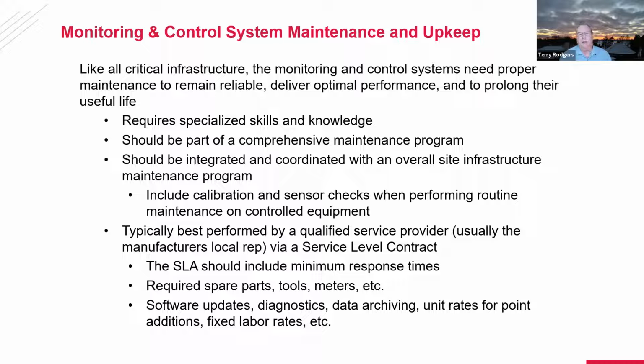I had an installation once and it was all commissioned, everything looked great. The system ran well, and then over time, it started to bog down. And I learned the difference between IP static and dynamic addresses, because it was supposed to have been configured with static addresses. So every time you brought on a device, it would have the same address, but it had been set up and configured for dynamic.